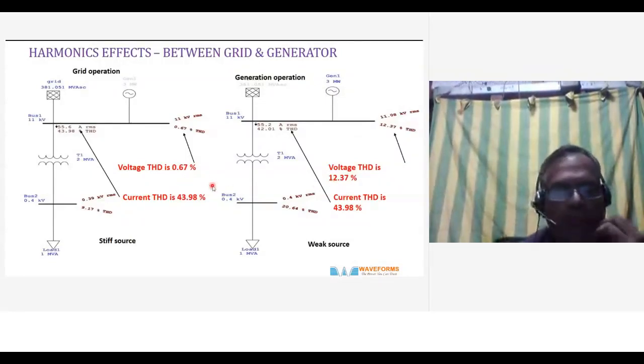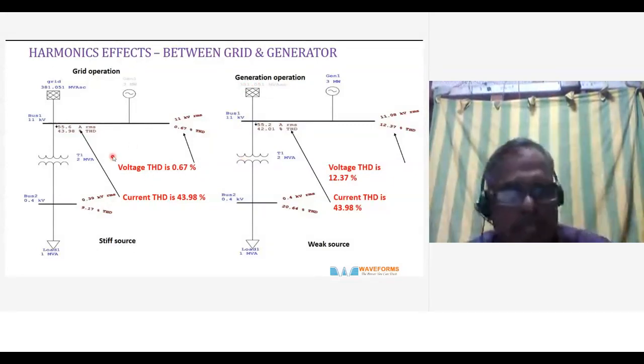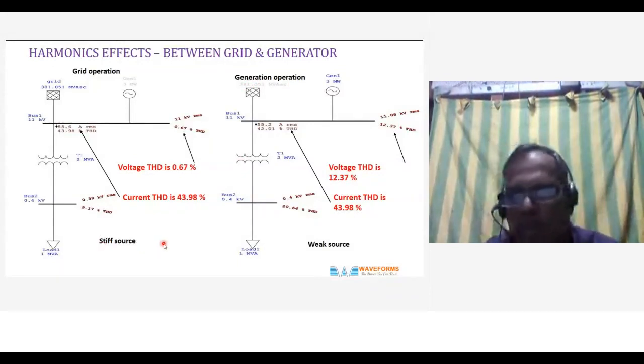That is because of the strength of the grid. It is a very strong source, and it has a very low impedance, so voltage does not get distorted. It's a very stiff source. But with the same harmonics on a generator of lower capacity, being a weak source with a high impedance, the voltage distortion is very high, 12.37%.